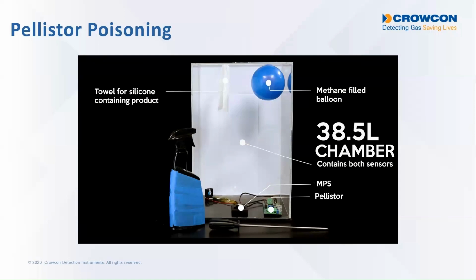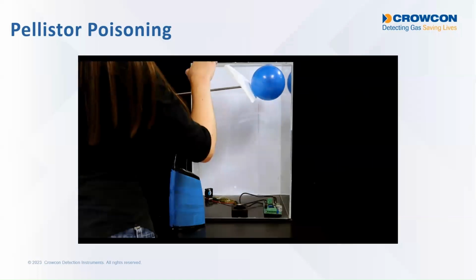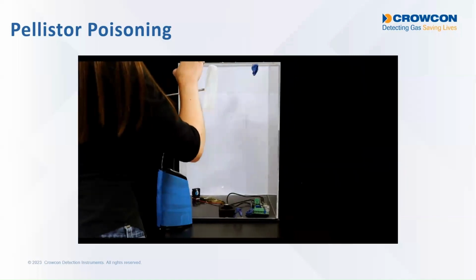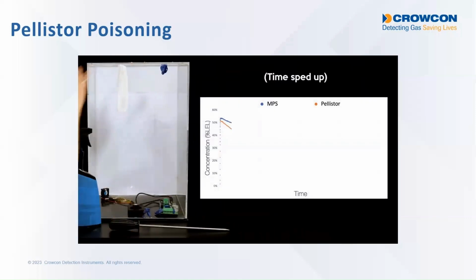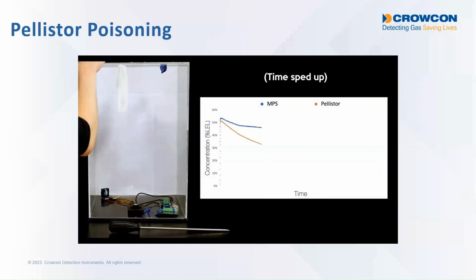And there's a towel there that the silicone spray will be sprayed onto. So the balloon is burst, and that chamber is now filling up with methane at about 50% LEL. And you can see the response from the two sensors. This is time sped up a little bit. But you can see there's a response from both sensors to the gas in the chamber, albeit the Pellistor response is lower than the MPS sensor response.